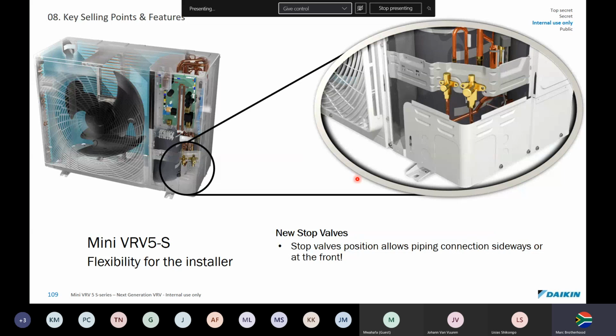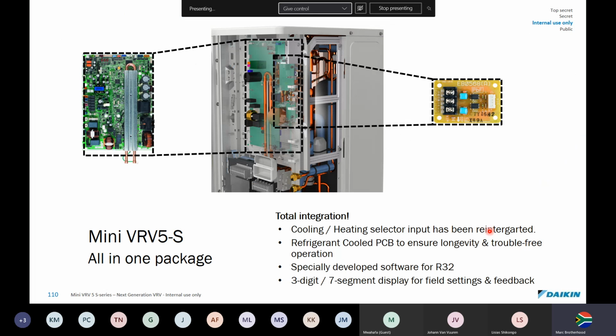The developers have also added valves now at 45 degrees instead of flush. I presume it adds some advantage to installers, when they feel it's easier to add and remove their hoses at a 45 degree angle. On the VRV5, the cooling and heating selector input has been reintegrated. In the past, you would have to buy that as an optional extra. So that has been reintroduced.